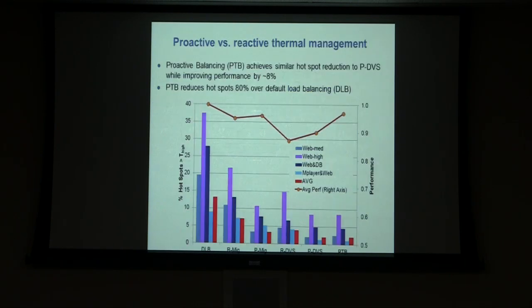When we implement this in a real system and compare it to default load balancing, our proactive thermal balancing decreases incidence of hotspots by about 80%. It does this with a relatively small performance hit, which happens only when you're in very highly utilized scenarios, in which case you either have to slow down or shut off, so you can't do much about it.